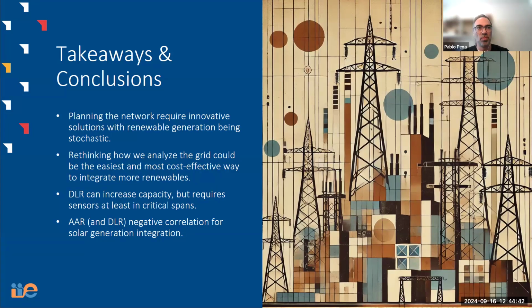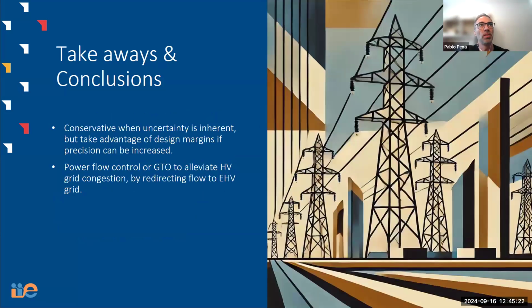Dynamic line rating can increase capacity. It's a fact. It's the truth, but it requires physical sensors, at least in critical spans, or weather stations in those cases. And ambient adjusted ratings and dynamic line ratings too have a negative correlation for solar generation integration. So take it into account if you intend to expand your system with solar generation.